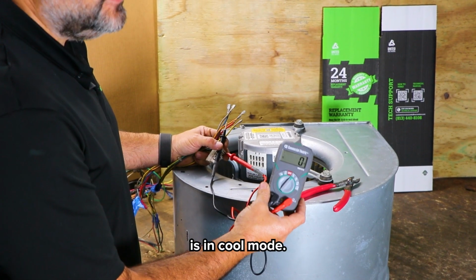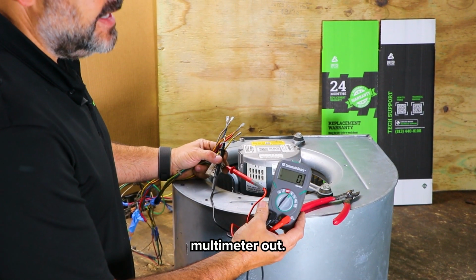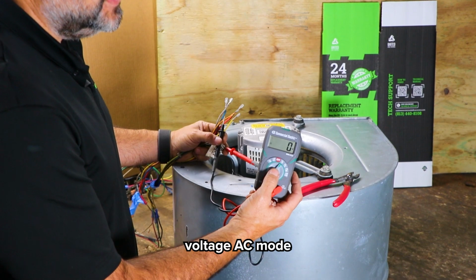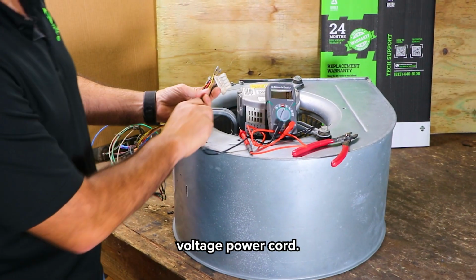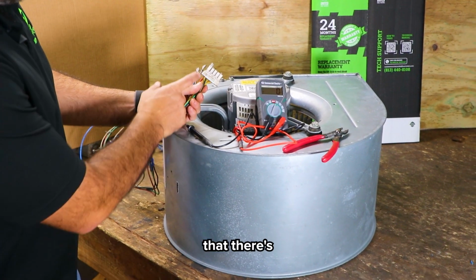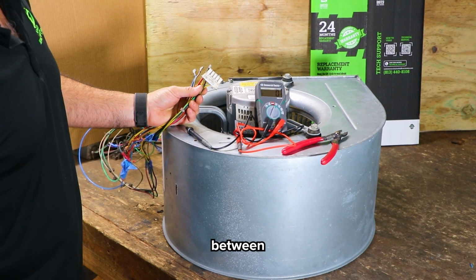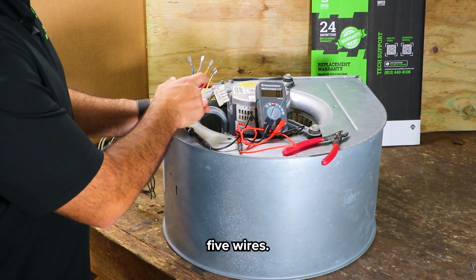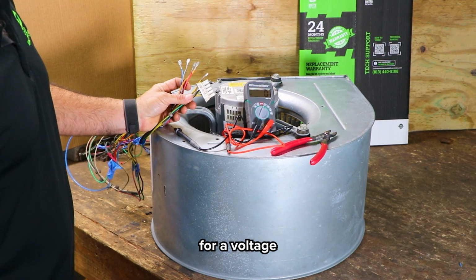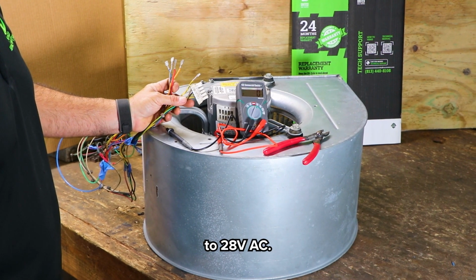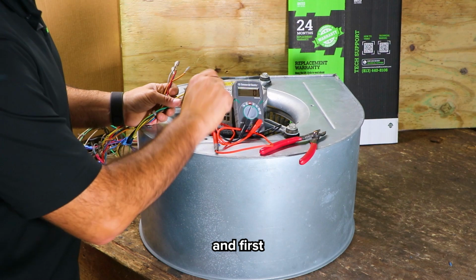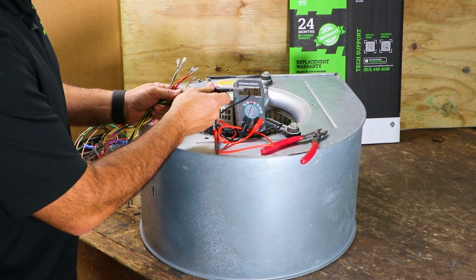Now that our thermostat is in cool mode, we're going to get our multimeter out and put it in voltage AC mode. On your high voltage power cord you'll see there's a letter C. We're going to test between the letter C and these 5 wires, looking for voltage between 21 to 28 volts AC. Let's first push our probe into the C.